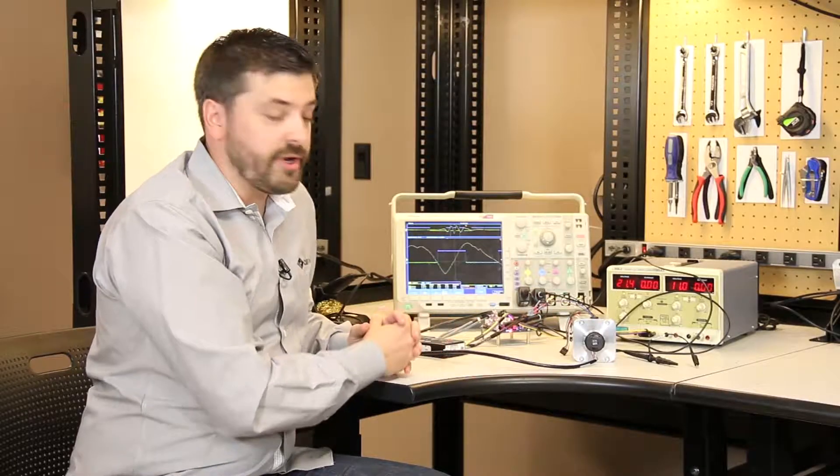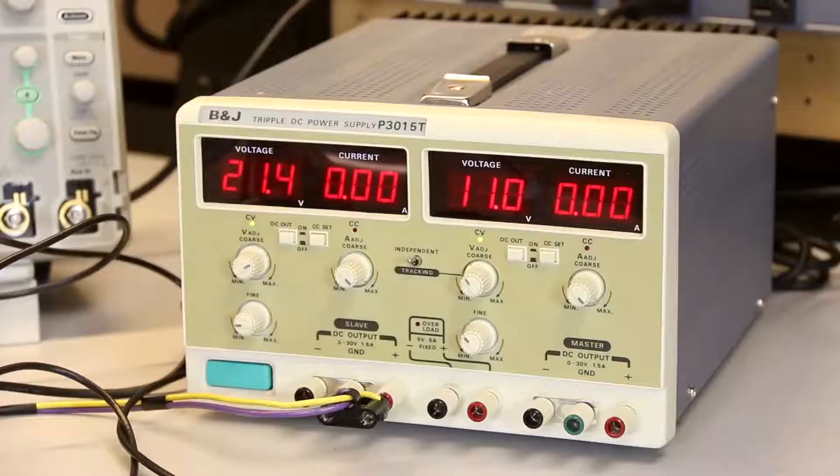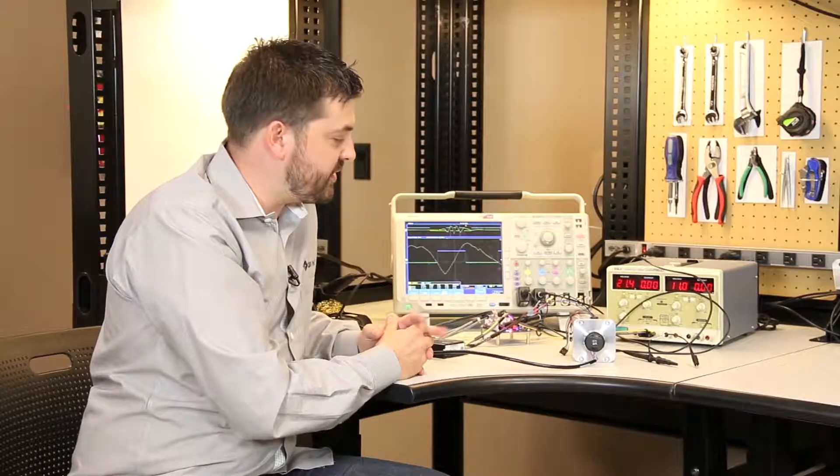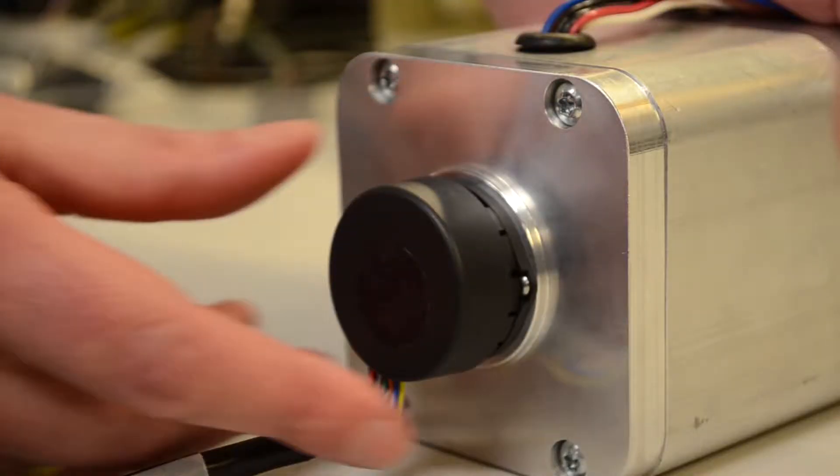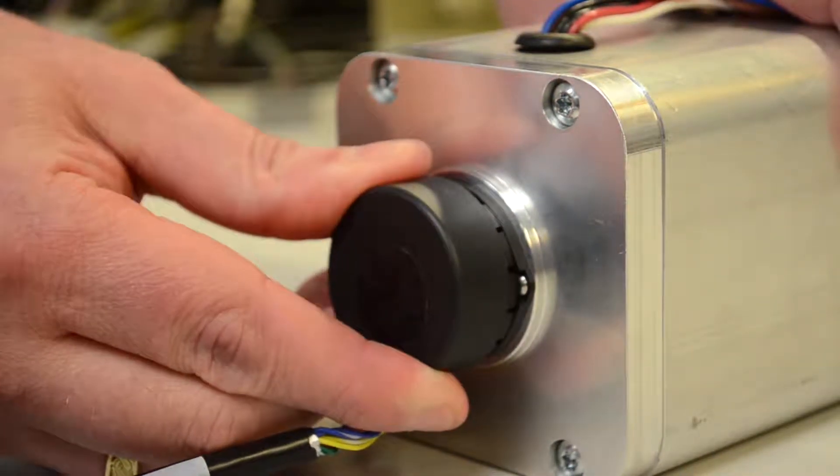Next, you need to take the motor and encoder over to a back EMF fixture. At the back EMF fixture you'll need a power supply, an oscilloscope, and during that process you iteratively adjust the encoder disc until you get a proper aligned back EMF signal.